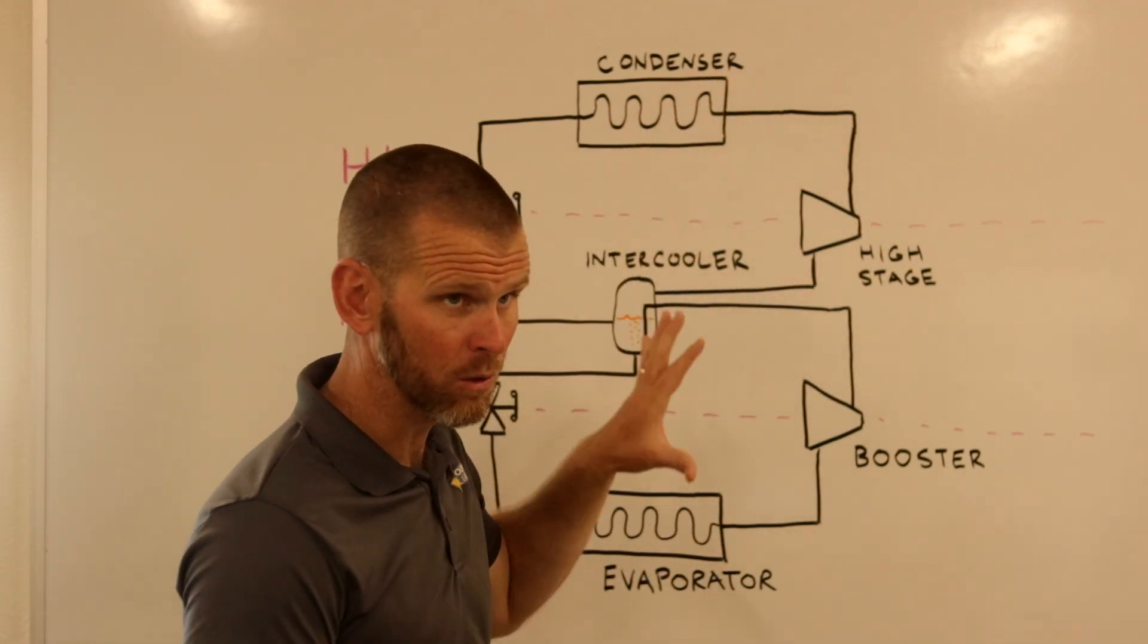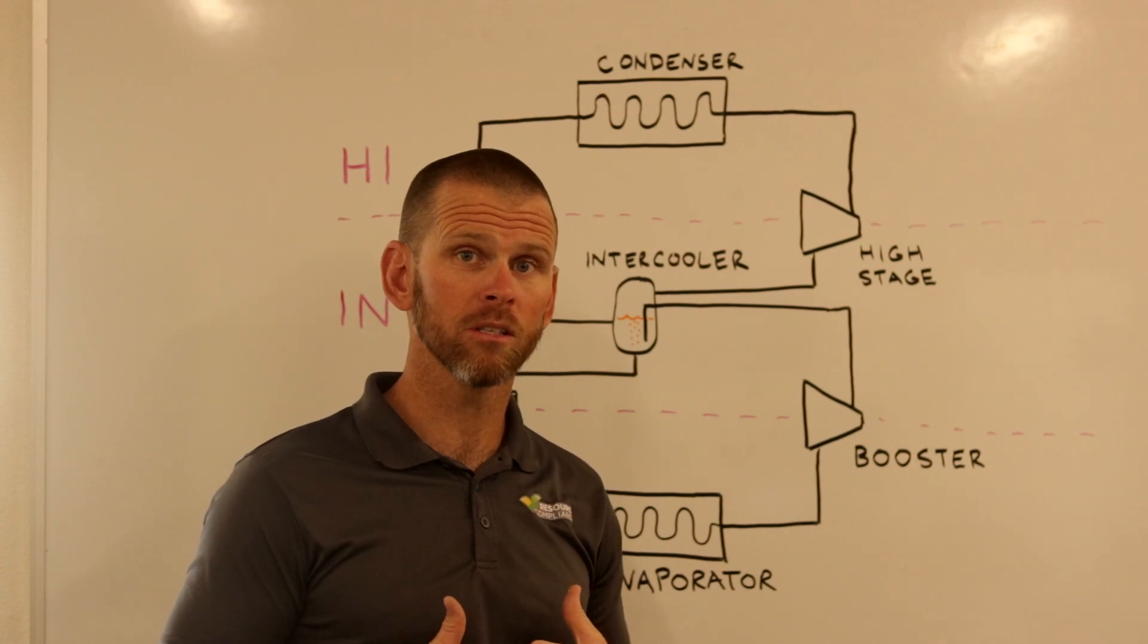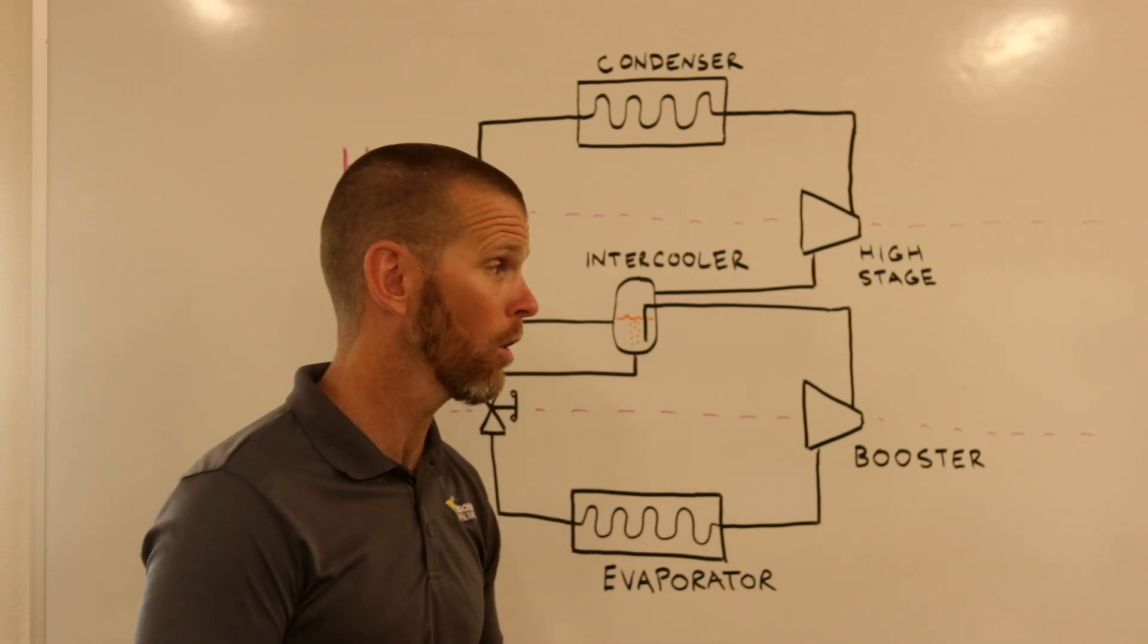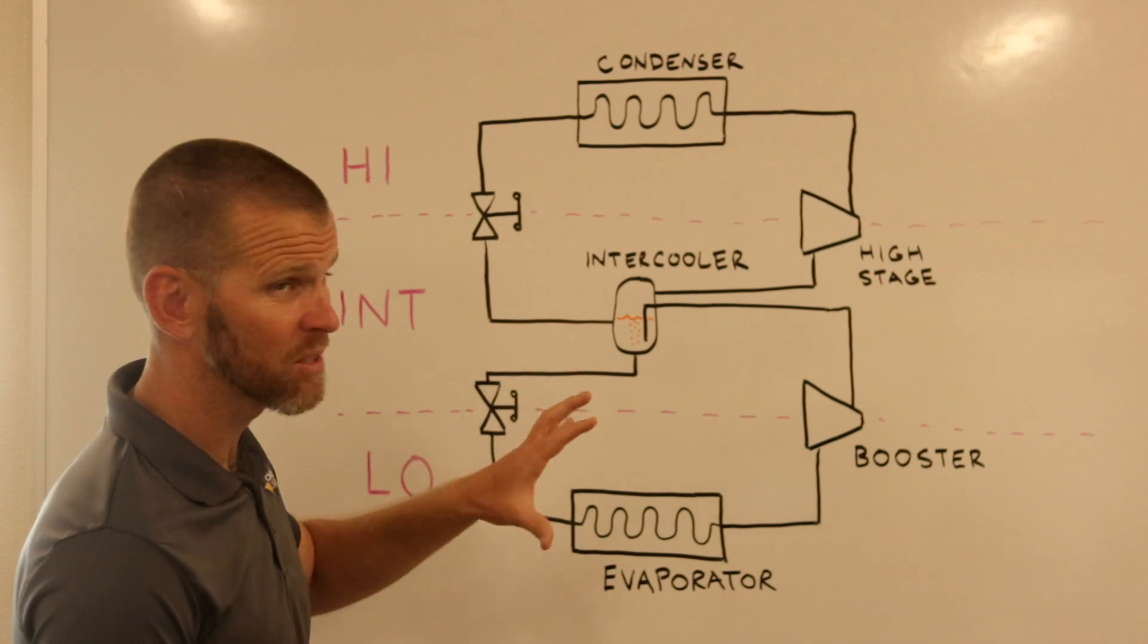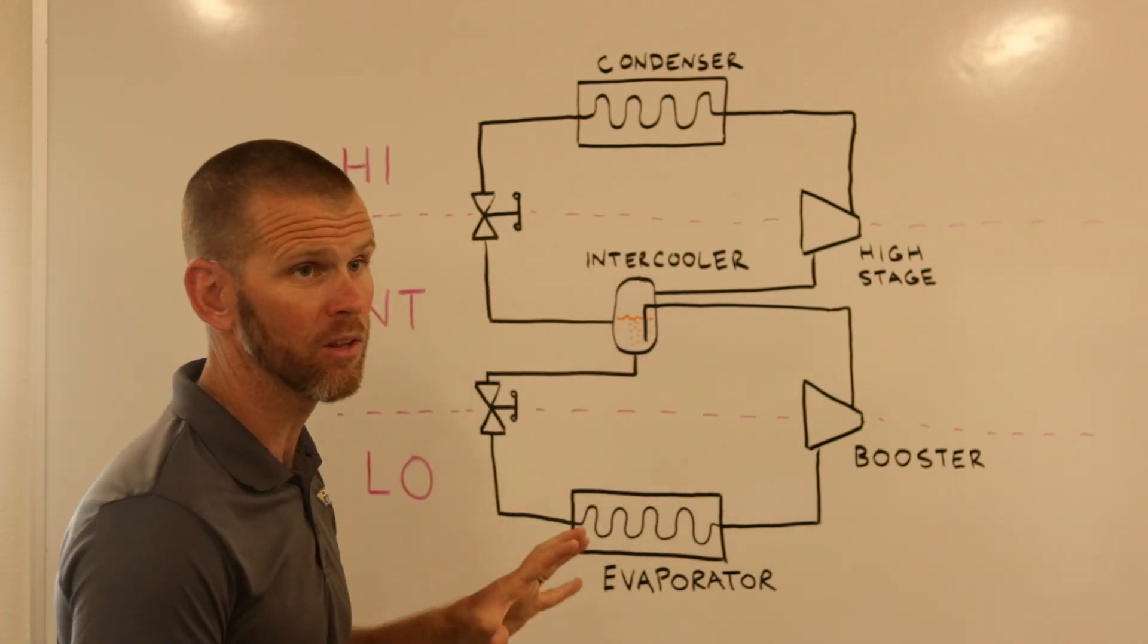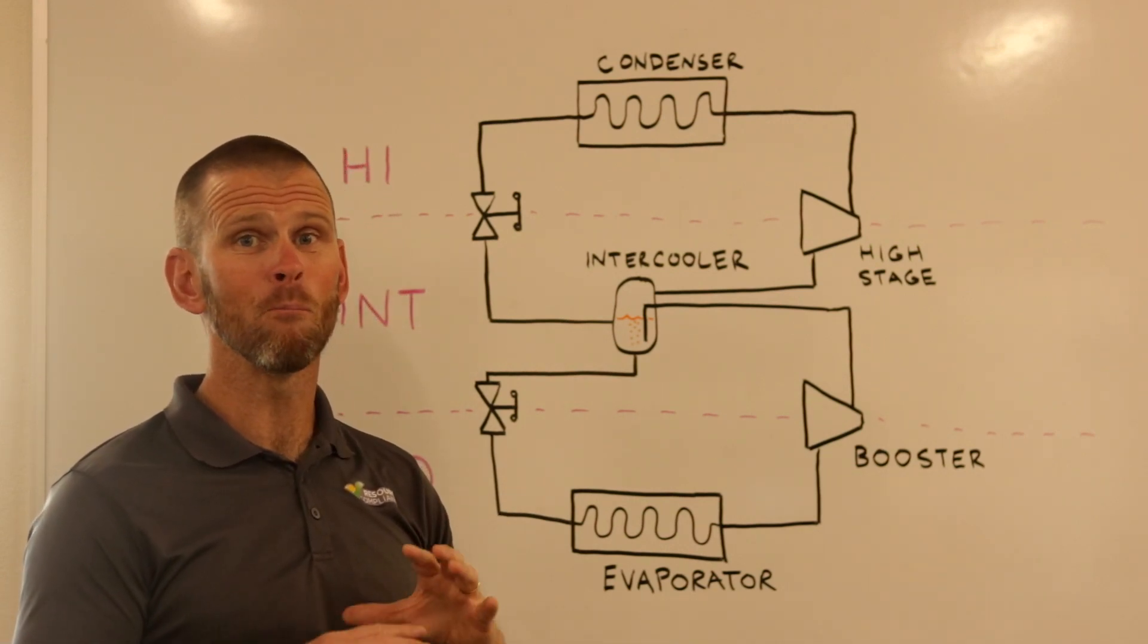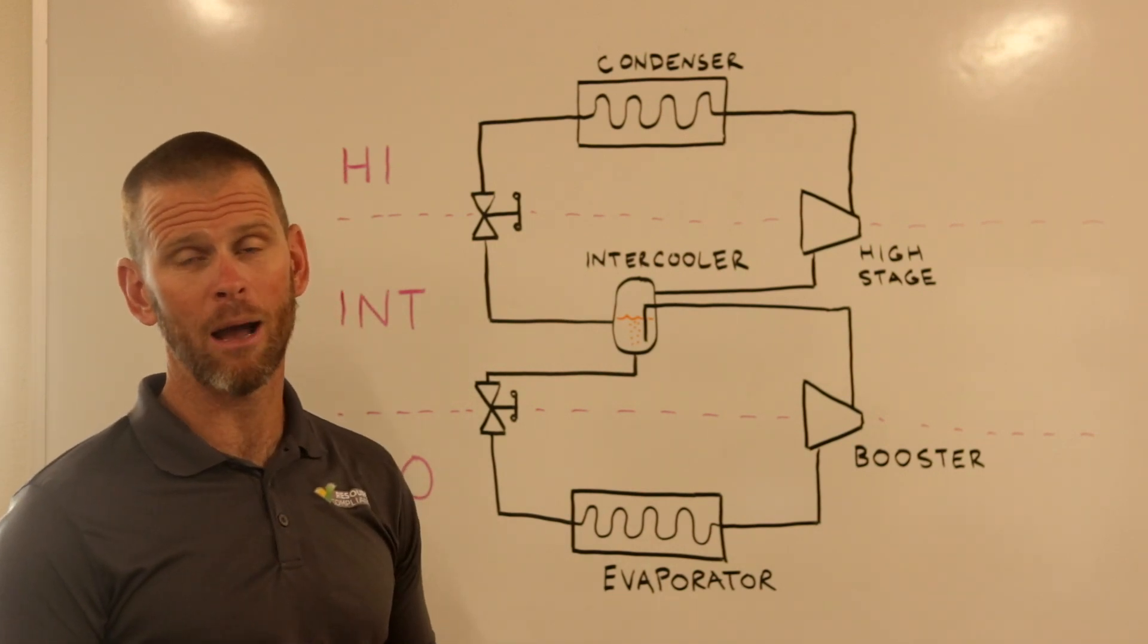By doing this, we drastically reduce the discharge temperature that's experienced right here, which is what we're aiming for. Furthermore, we operate more efficiently because of some of the various things I already discussed. For example, the flash gas not going through the evaporator in our first expansion valve. So two-stage systems are pretty much mandatory when it comes to very low temperature applications.